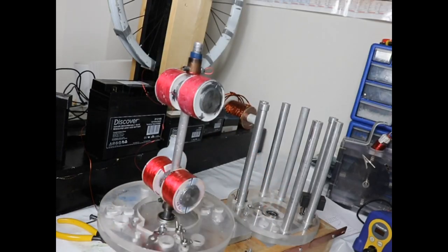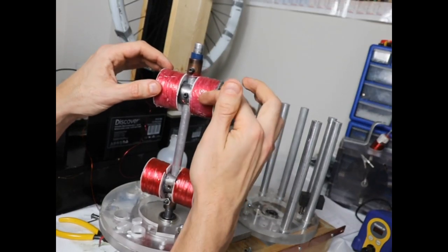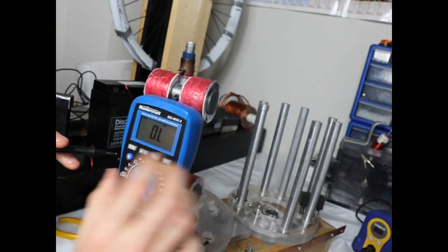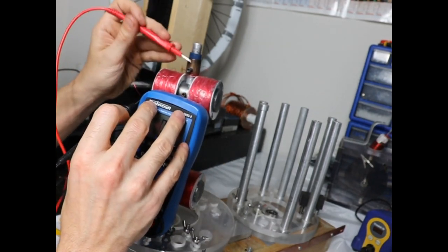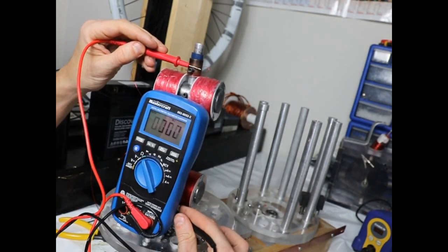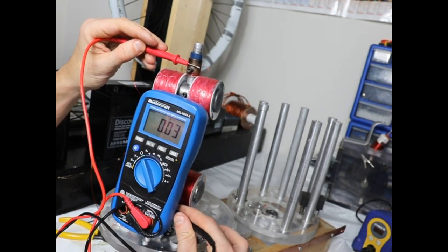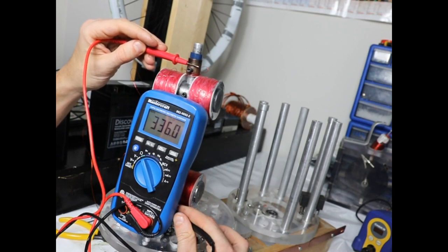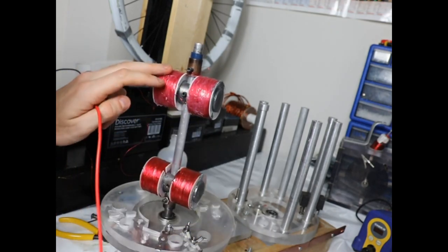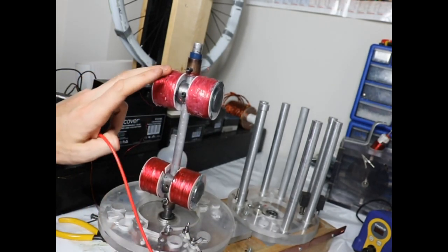And now I've got all my connections made. I've got the coils connected to the slip rings and one another. That's the last thing I need to do. So there's one slip ring and I'll touch the other slip ring. There we go, 336, roughly 336, so 340 we'll call it ohms of resistance in the coil.